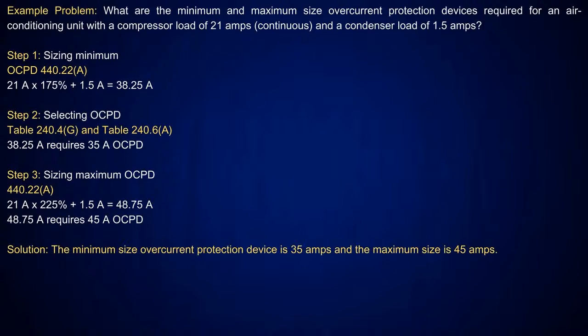Okay. Right. Now here's an AC unit. So I've got a compressor load of 21 amps and a condenser of 1.5. Same principles apply here. When I look at this, I'm going to look over at 440.22. Now, some of y'all that have your 2023, because we're doing this on 2020, but I do like to tie in the 2023 if there's a change that's made. When you go over and look at 440.22A, they sort of did it like they had it in the last cycle. I expect this eventually to be 440.22(A), (B), and (C).